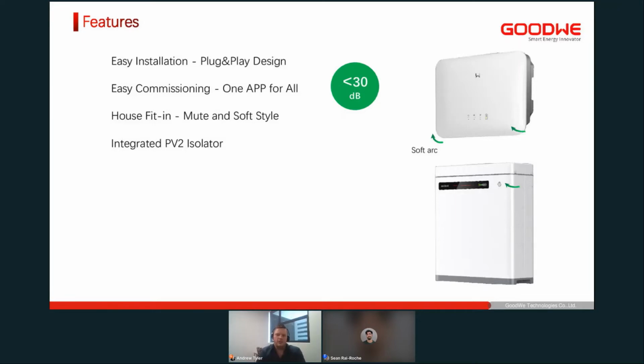With fans, you would have a challenge putting it in your lounge or in a place where you want your friends and family to see, but this does fit into the home really well and also looks aesthetically pleasing. And then also we do have an integrated PV DC isolator, which, depending on which model you buy, you would be either isolating 1 or 2 MPPTs. The 3 kilowatts in our range has 1 MPPT. The 3.6, 5, and 6 have 2 MPPTs.